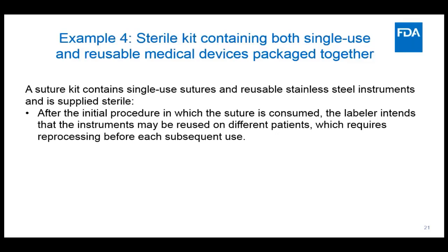Okay. Well, I need to go back to your original question, though, because you said requires a UDI. They all require a UDI. The convenience kit exception is not whether the kit requires a UDI. All kits require a UDI. All devices require a UDI. The exception is whether, if it qualifies under the exception, the individual constituents within the kit require a UDI. I need to make that really clear. That's why we're saying that with the sterile kit, once it's open, all the constituents in there are compromised and the whole thing gets thrown out. Now, the question of what happens when you make a revision to a kit and whether that requires a new DI goes back to whether you consider that a new version or model of the device.